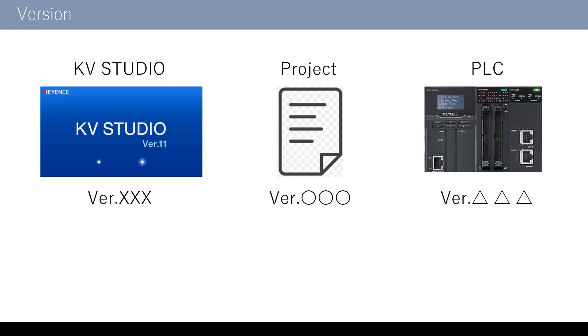Now let me explain about versions of projects and the PLC. When the versions of the project and the PLC are the same, or when the version of the PLC is higher, you can transfer the project just fine. You should keep the KV Studio version always the latest. Then you can smoothly transfer and edit any old projects. Moreover, you can find a project from a PLC with an old version and transfer the project.